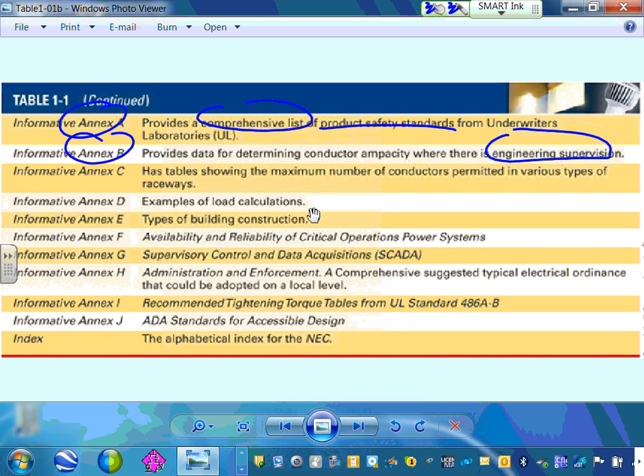Annex B, engineering supervision. Say you have 24 ducts underground, all carrying 500 kcmil, 4 conductors each. How much current can each duct carry? Nothing in any code book can tell you that right now—that's engineering supervision, which is what you do at an engineering college. That annex is really interesting when you work for an engineering firm. That's taking it to the next level, after you know how to use the code.